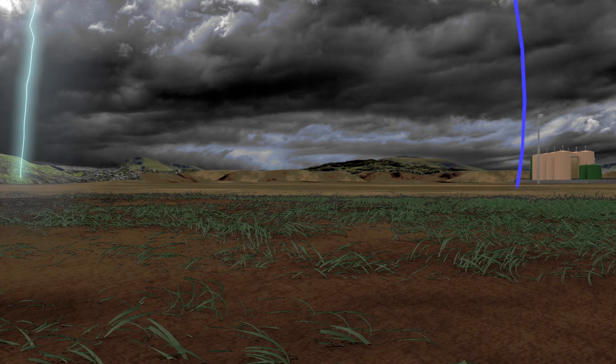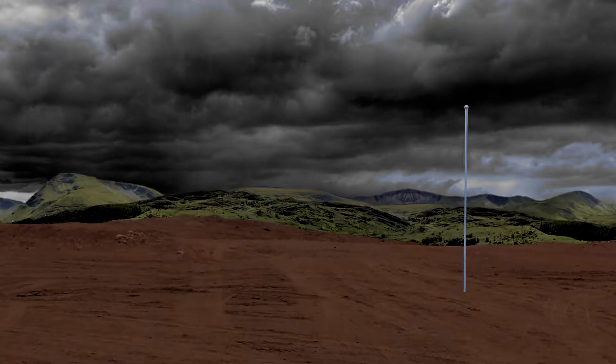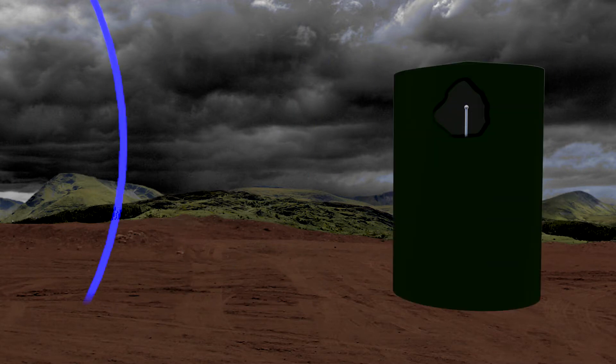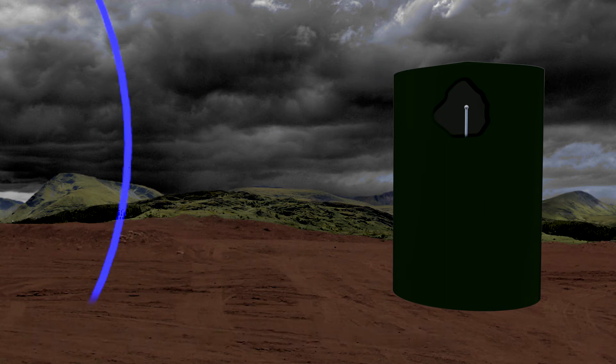The principal effect of a nearby lightning strike is exposure to intense electromagnetic, or EM, waves. If lightning should strike close enough, electromagnetic waves would induce sparking onto this flagpole. The fact that the flagpole is well-grounded does not prevent sparking. If we placed the flagpole inside a metal enclosure of adequate construction, that would prevent sparking, because metals are effective electromagnetic shields.